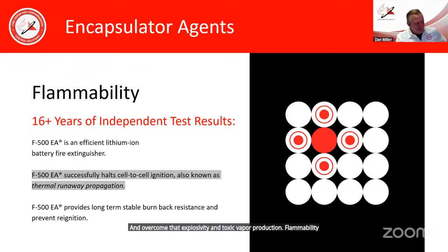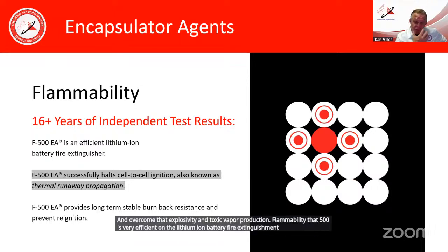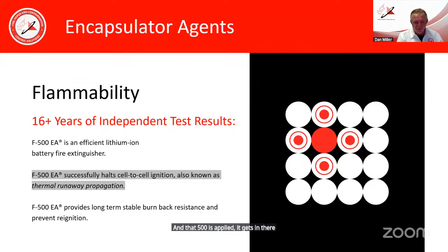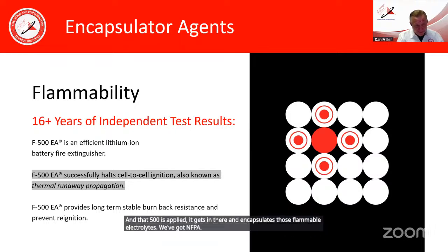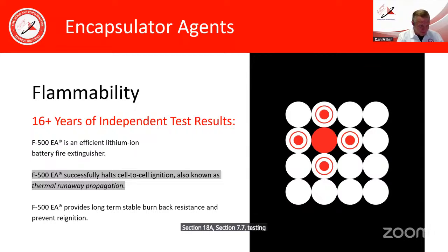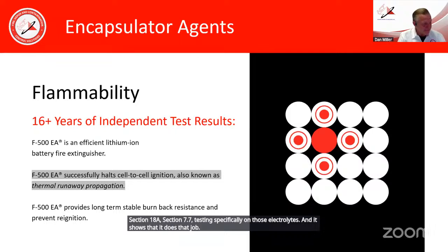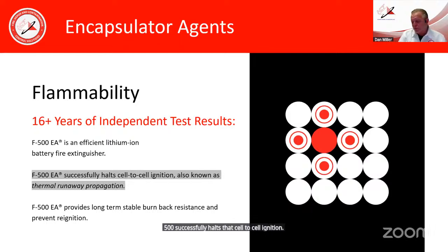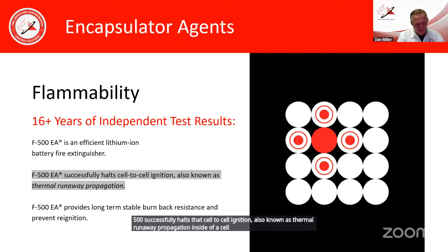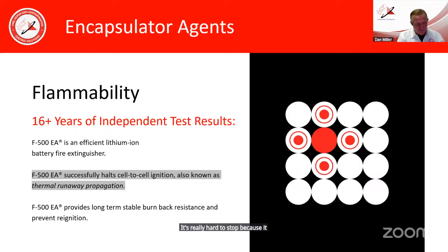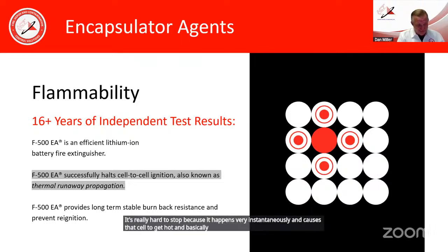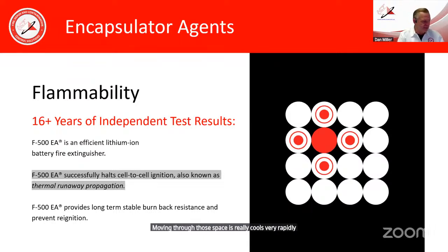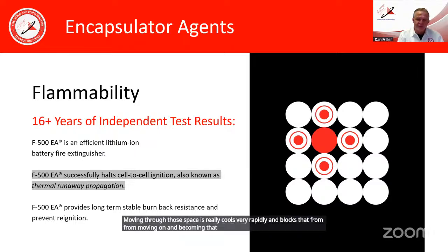Flammability: F500 is very efficient on lithium-ion battery fire extinguishment because it gets in between the cells and the layers of the cells. If those cells open up and F500 is applied, it gets in there and encapsulates those flammable electrolytes. We've got NFPA 18A Section 7.7 testing specifically on those electrolytes showing it does that job. F500 successfully halts cell-to-cell ignition, also known as thermal runaway propagation. Inside a cell, thermal runaway from layer to layer is really hard to stop because it happens almost instantaneously, causing the cell to get hot and basically self-destruct within seconds. But that propagation from cell to cell is cooled very rapidly by F500 moving through those spaces, blocking it from becoming an endless chain reaction.